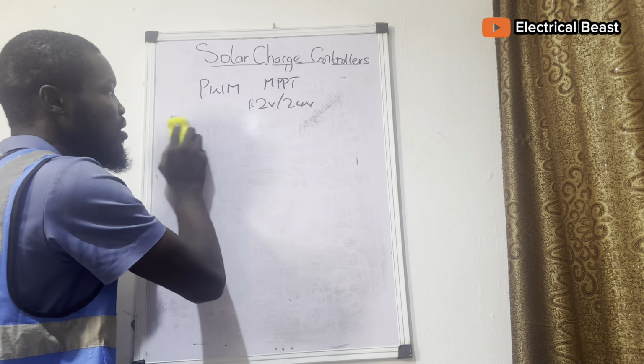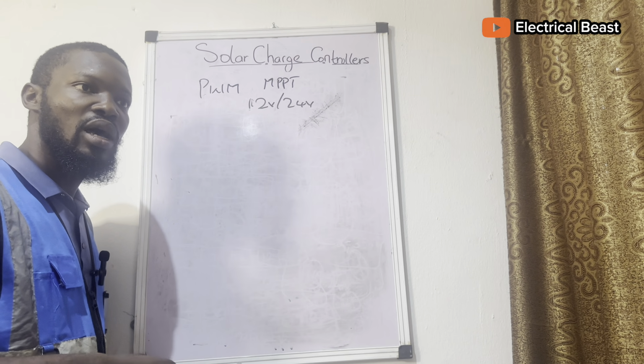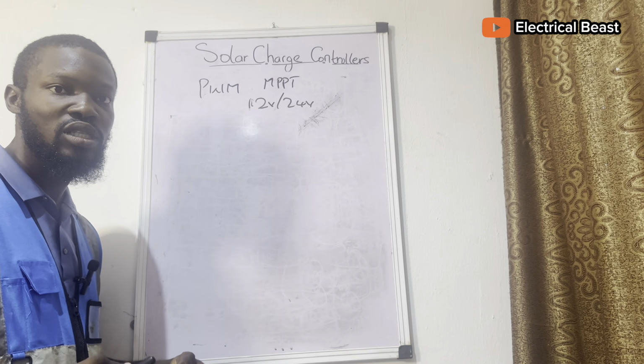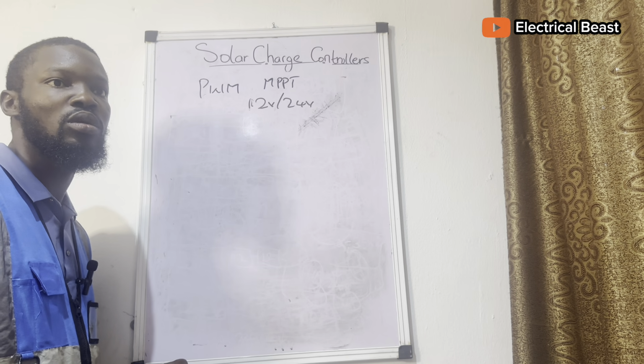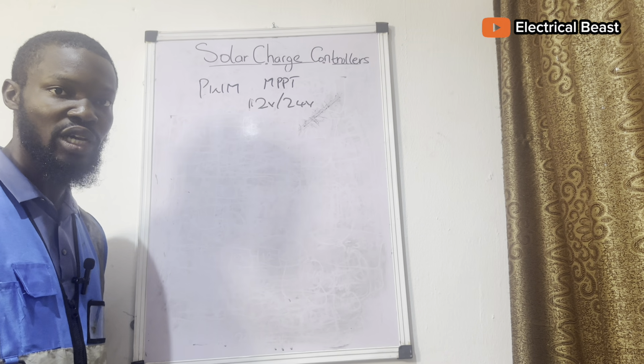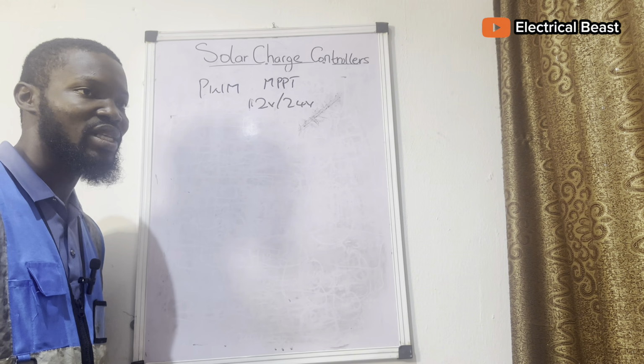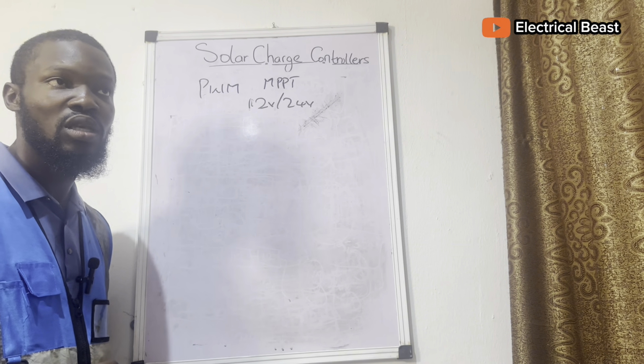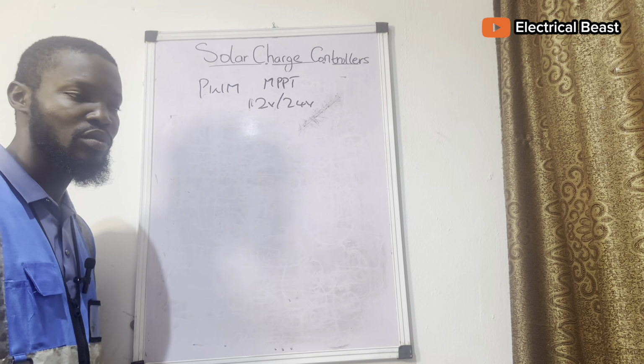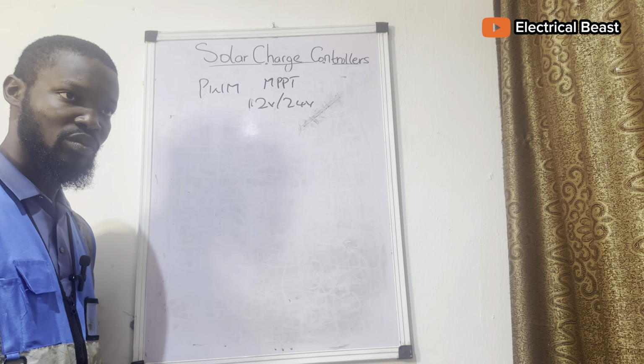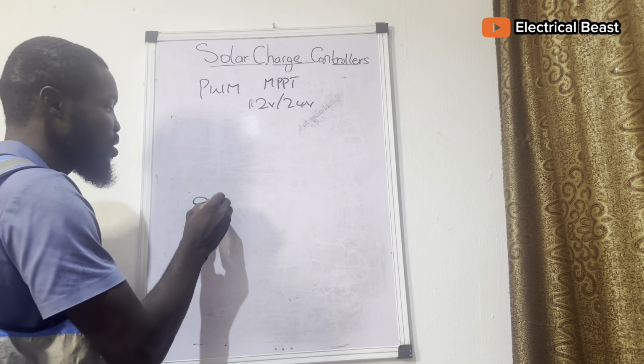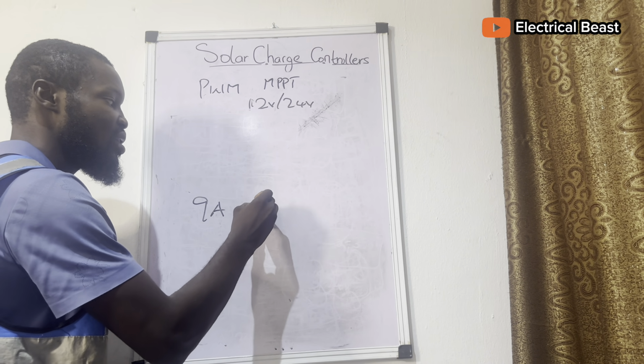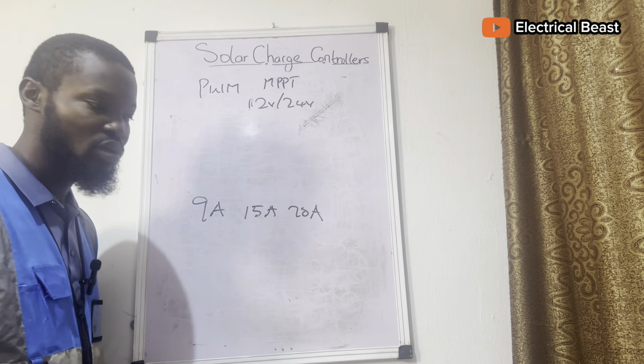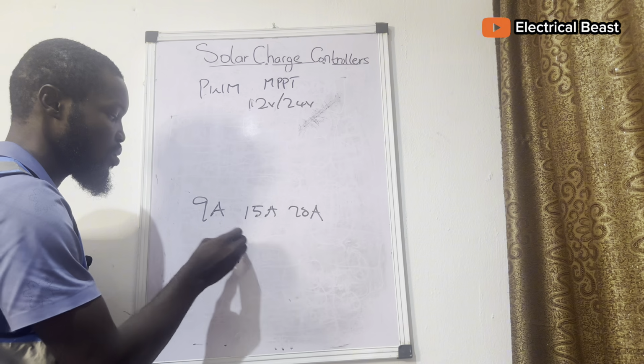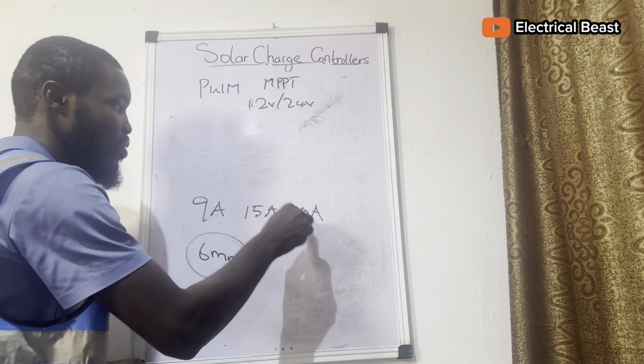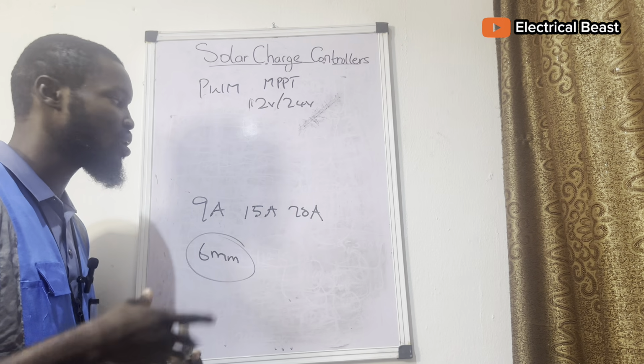And one thing you need to know about parallel connection is that when you connect systems in parallel, as the current increases, you need to ensure that the cable size, the DC cable you are using to transmit the current to the battery to charge, is big enough to accept whatever current is entering. But PWM systems are mostly small systems, so you don't need to worry much about how big the cable size is. If you have 9 amps going to your battery, maybe at best 15 amps, 20 amps, you can use, let's say, a 6 mm cable for that. You can accept these currents, understand? So for your PWM charge controllers, that's that for PWM.